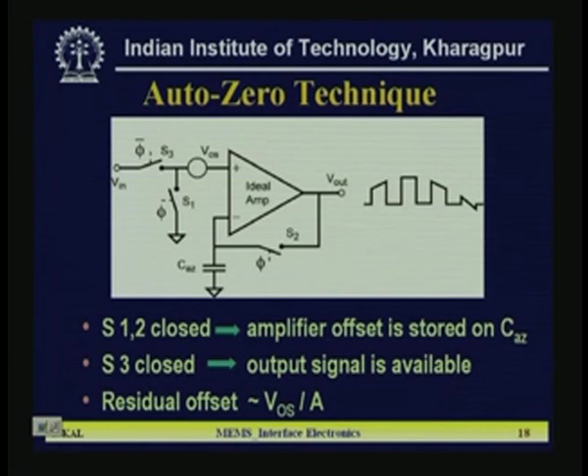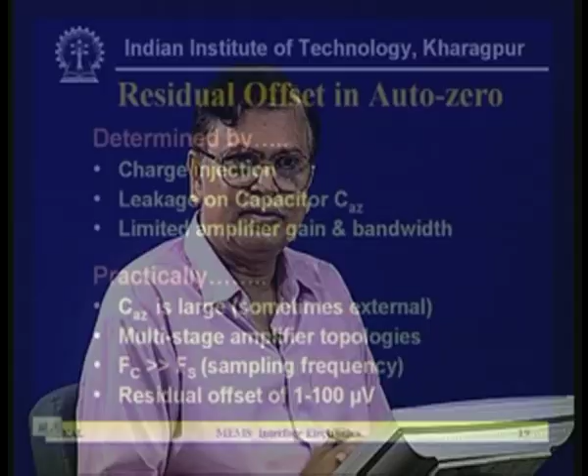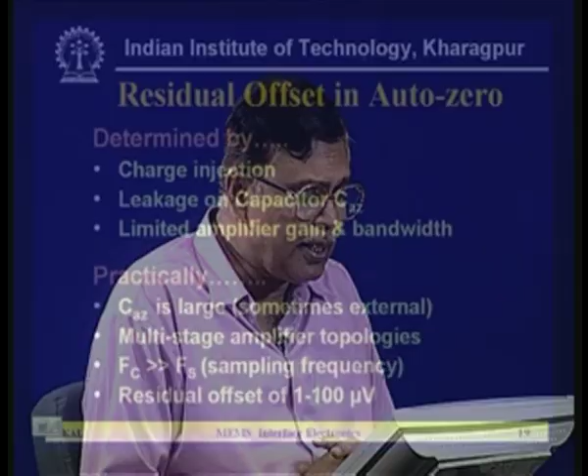Now this residual offset in the auto-zero technique is determined by three parameters. One is charge injection, how the capacitance CAZ is made, how you charge the capacitance. Leakage on the capacitor, leakage should be as small as possible so that the total offset can be stored there initially. And limited amplifier gain and bandwidth. These are the determining factors in this auto-zero technique.